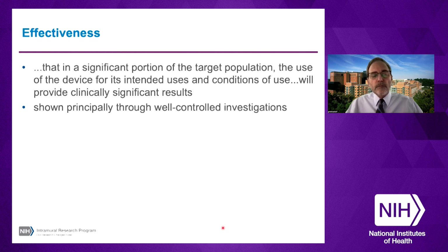Effectiveness, on the other hand, means that in a significant portion of the target population, the use of the device for its intended uses and conditions of use will provide clinically significant results. The point here is that you can make something that carries out an action and show that it does that action, but if there's no benefit, there's no effectiveness, then it really is not suitable for marketing. So it has to have a clinical benefit. Otherwise, there's nothing to outweigh any risks.